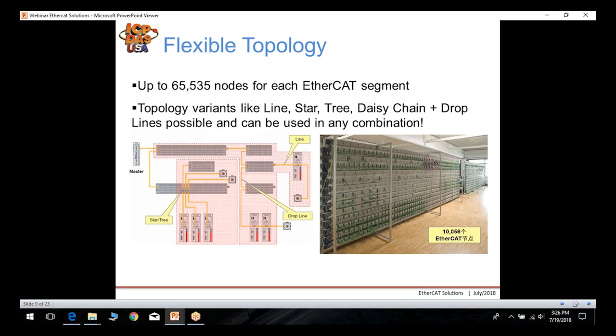EtherCAT has a very flexible topology. You can have up to 65,535 nodes per EtherCAT segment, and the topology varies — traditional line, star, and tree. In addition, you can use daisy chain and drop lines in any combination, as long as you connect the nodes one by one. Additional networking accessories can implement more complex networks, including configurations with 10,000 or more EtherCAT nodes.